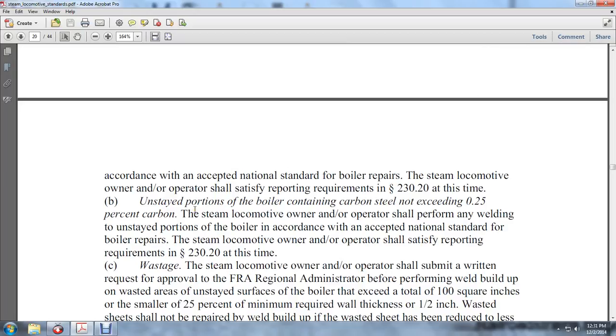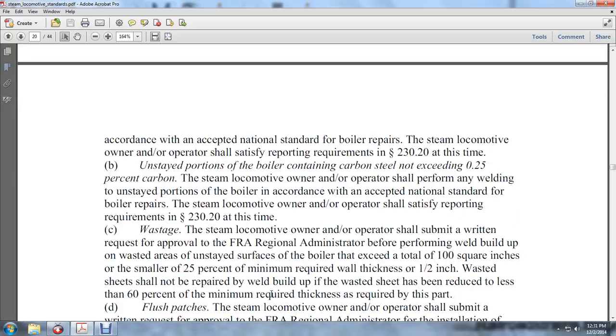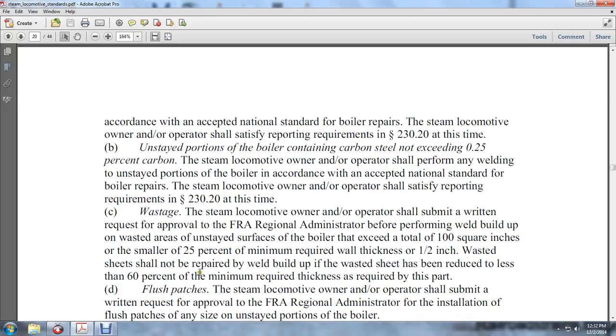For unstayed portions of the boiler containing steel with less than 0.25 percent carbon, the steam locomotive owner and operator shall perform any welding of unstayed portions according to accepted national standards for boiler repairs and shall satisfy the reporting requirements of 230.20. A written request for approval from the FRA regional administrator is required before performing weld build-up on wasted areas of unstayed surfaces of the boiler exceeding a total of 100 square inches. The 25 percent minimum required thickness or 1/2 inch for wasted sheets shall not be repaired by welding if the sheet has been reduced to less than 60 percent of the minimum required thickness.